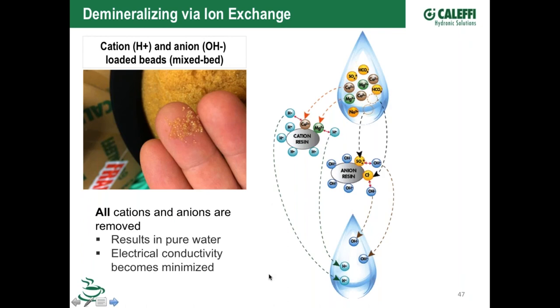So another question that came in is, what about if my city water has chlorine in it? What will happen? We saw from an earlier slide that water coming from a municipal water supply with chlorine is governed by national safety standards to keep that chlorinated content to a minimum level. I think the stainless steel boiler manufacturer spec shown earlier said chlorine should be kept below 5 parts per million, or 5 milligrams per liter, and that's higher than what municipal city water will allow their water to get to. So it shouldn't be an issue, even though you might be able to taste it.